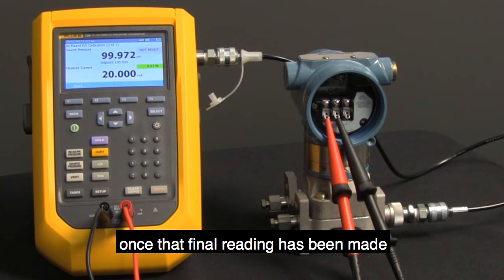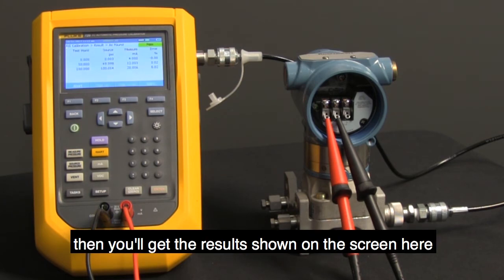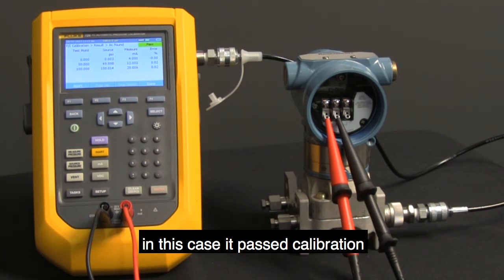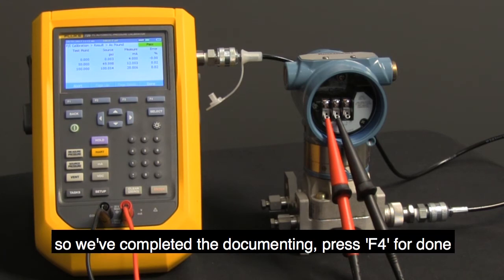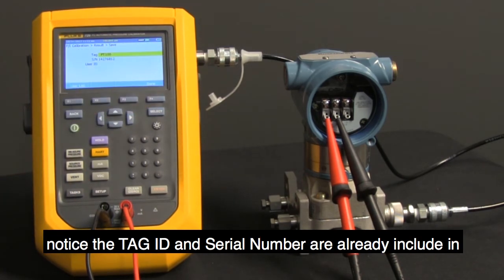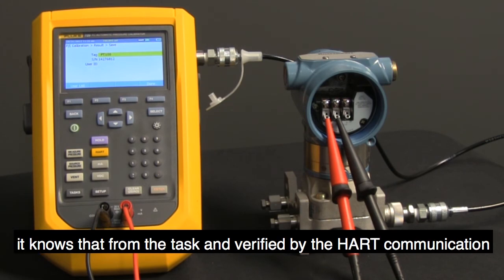Once that final reading has been made, then you'll get the results shown on the screen here. In this case, it passed calibration, so we've completed the documenting. Press F4 for done. Notice the tag ID and the serial number are already included. It knows that from the task and verified by the HART communication.